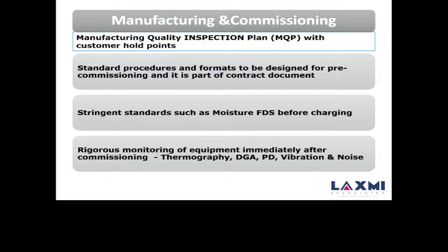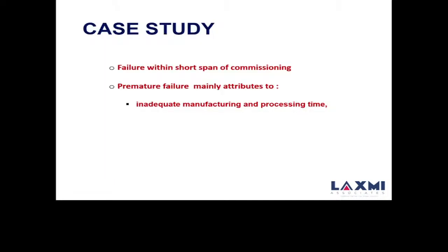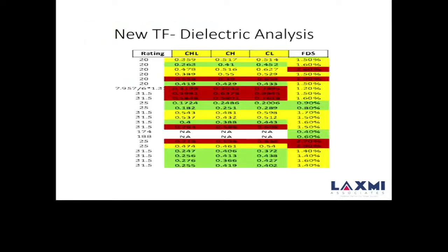And then rigorous monitoring of the equipment immediately after commissioning, like thermography, DGA, partial discharge, vibration, noise, till the transformer gets settled down. A fingerprint should be there, because infant failure is very much prevalent in our system till the transformer gets acquainted with the system and settles down. It could be some commissioning error, some component issues, some structural problems, some kind of teething problems that could be identified. So online monitoring by these techniques is very helpful once the transformer is charged.